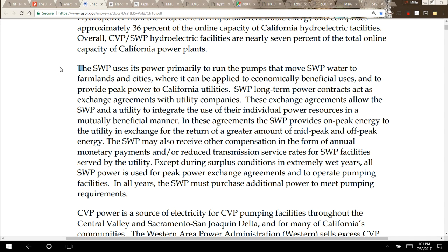In these agreements, the State Water Project provides on-peak energy to the utility in exchange for the return of a greater amount of mid-peak and off-peak energy. The State Water Project may also receive other compensation in the form of annual monetary payments and/or reduced transmission service rates for State Water Project facilities served by the utility.